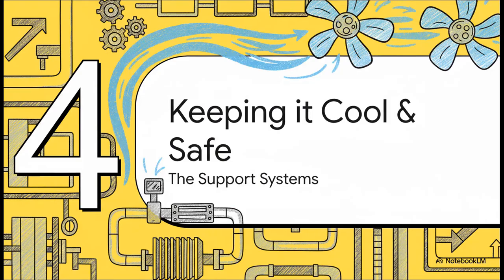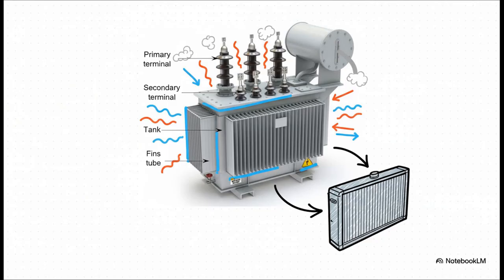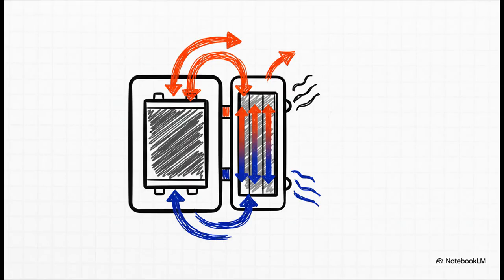So we know how it works, but how does it keep from overheating and failing? That's where the support systems come in. Remember all that heat from copper loss? To get rid of it, the transformer has its own cooling system. The fins you see on the side work just like the radiator on a car. Inside the tank there's a special oil that does two jobs at once: it insulates the components and absorbs heat. As that oil gets hot, it circulates out into the fins, and the huge surface area lets the heat escape into the air. Then the cooled oil cycles right back in.